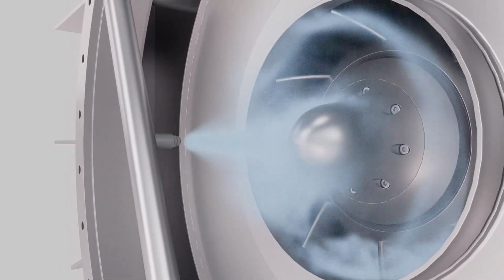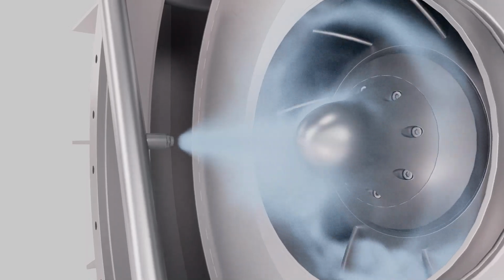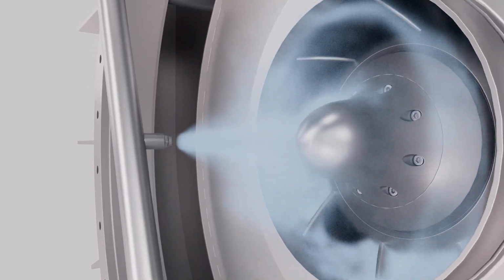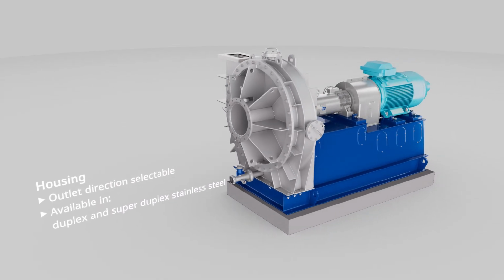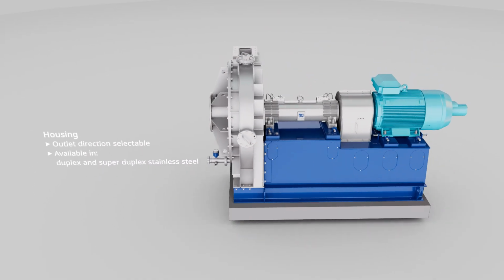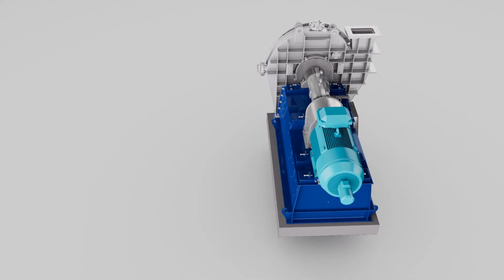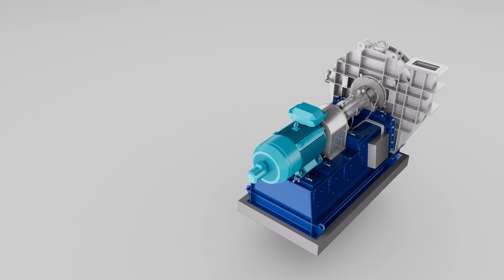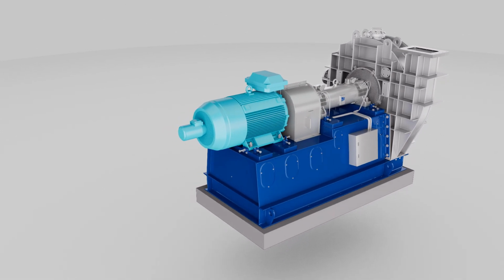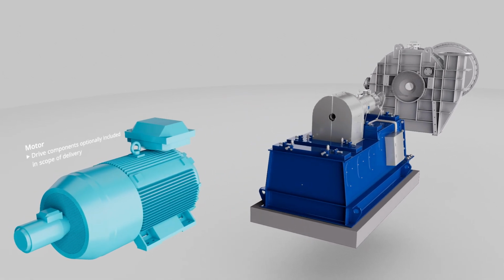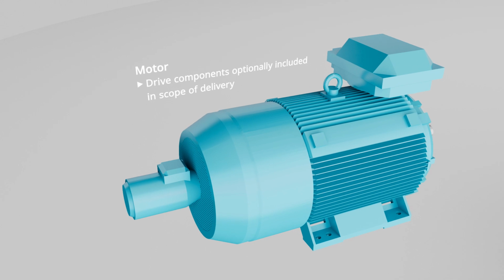Surplus water collects in the fan housing and is discharged through the automatic condensate drain, which is a standard feature on TLT turbo fans. TLT turbo fans are supplied on a base frame and can be installed and commissioned with minimum effort. This is thanks to the impressively simple system design. Let's take a look at some key components. The fans are most commonly driven by electric motors that can reach speeds of up to 6,500 revolutions per minute.